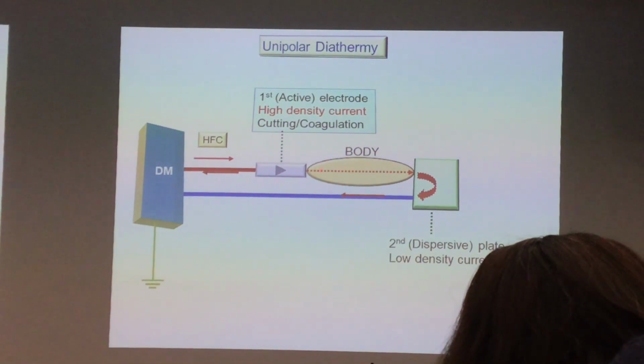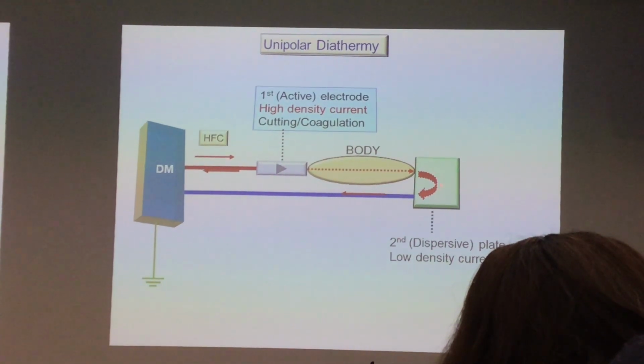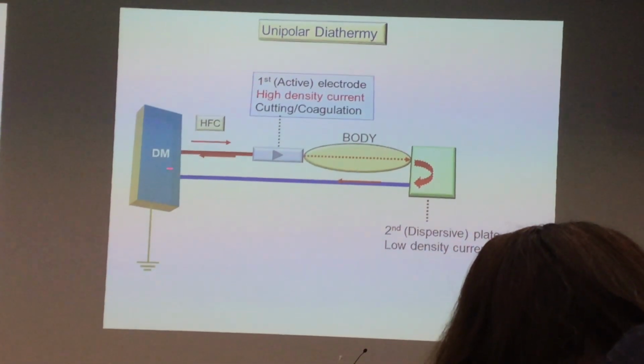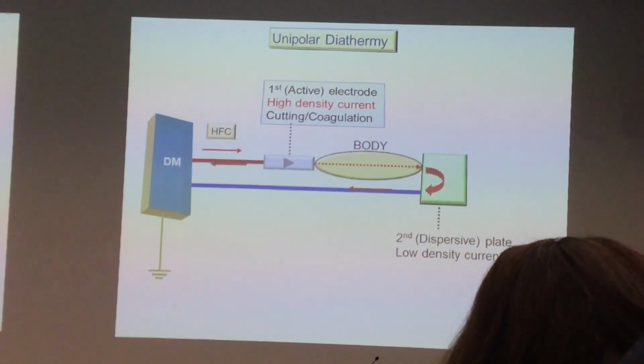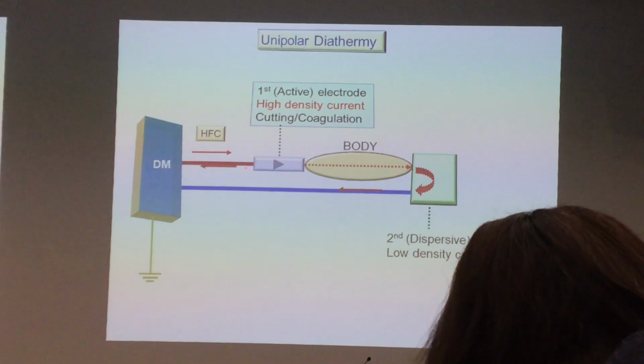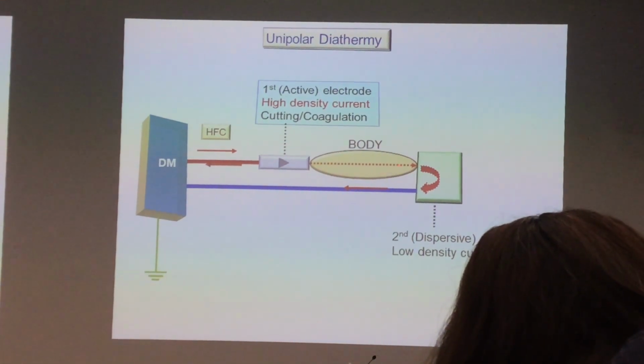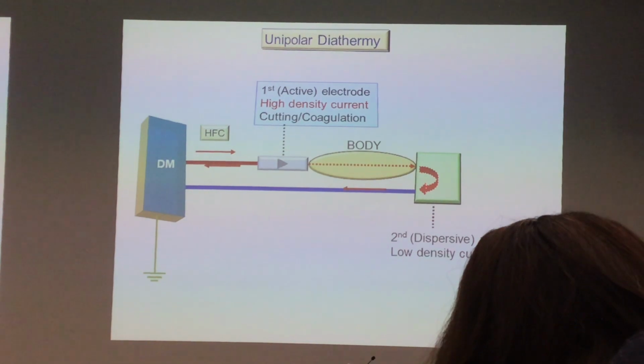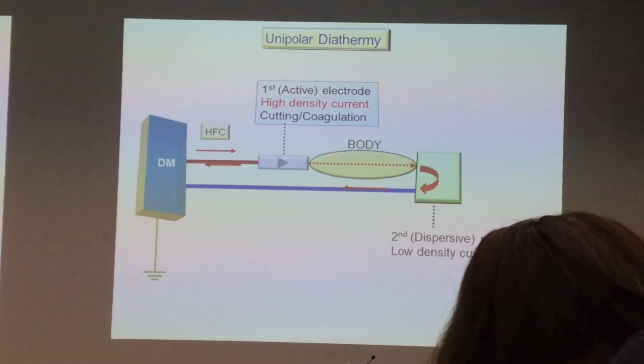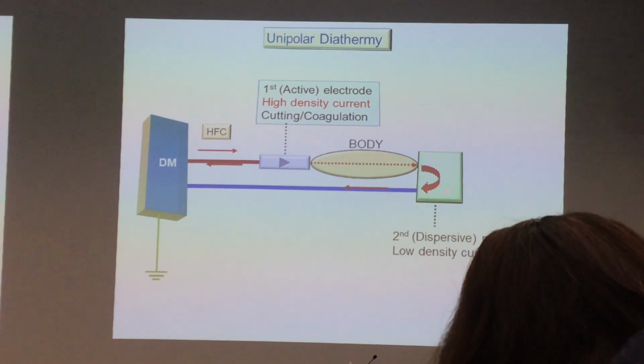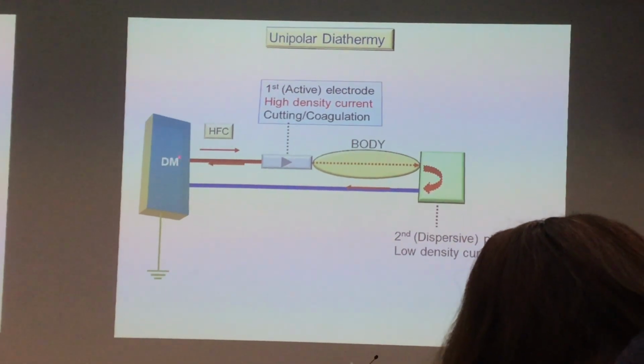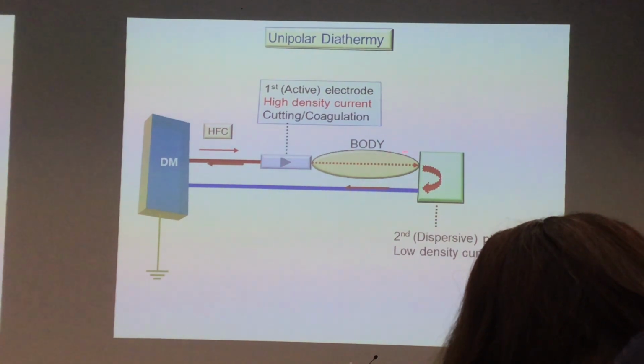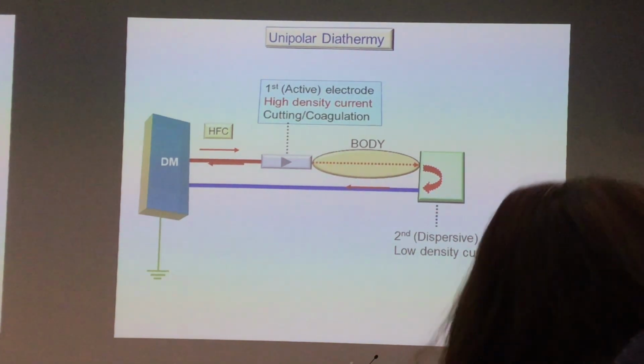You cut, you coagulate, and the current will return to the diathermy plate. So this way the circuit is complete. Machine, probe, skin, cut, coagulation. This is the diathermy plate. You put it on the thigh, for example, to disperse the current, and it goes back to the neutral, back to normal. So this is called unipolar, whereby the circuit is complete. It goes from the machine to the probe, to the body, to the diathermy plate, back to the machine. It's a complete circuit. So this is called unipolar, meant for cutting and coagulation.